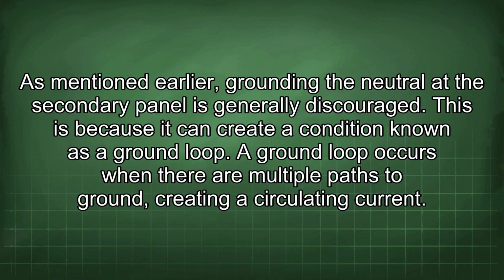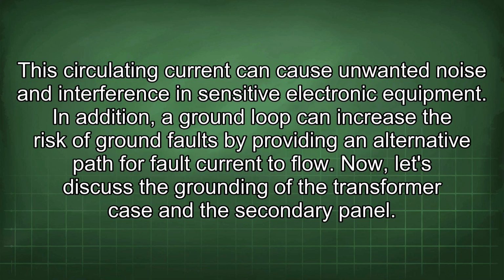As mentioned earlier, grounding the neutral at the secondary panel is generally discouraged. This is because it can create a condition known as a ground loop. A ground loop occurs when there are multiple paths to ground, creating a circulating current. This circulating current can cause unwanted noise and interference in sensitive electronic equipment. In addition, a ground loop can increase the risk of ground faults by providing an alternative path for fault current to flow. Now let's discuss the grounding of the transformer case and the secondary panel.